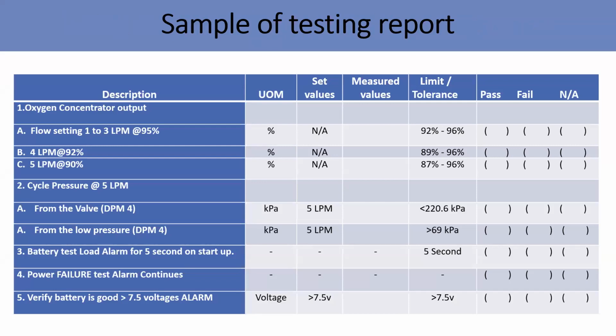Sample of test report. When you talk about an oxygen concentrator, normally you set your flow setting at 1 to 3 liters per minute, and you see whether the reading is at 95%. The tolerance is 92 to 96. When your flow changes, your purity reading will change as well. The higher the flow, the lower the purity reading can be. Remember that. And the cycle pressure, you get from the low pressure valve and from the high pressure valve. These basically depend on the brand and the model. Some will give you a low pressure measuring point and a high pressure measuring point. Some only give a low pressure measuring point.